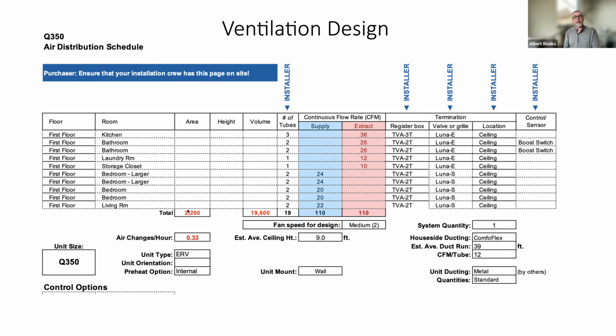It'll start getting dry, and it'll show up by cracked lips and skin and just general discomfort. So that happy medium we want to design for is we want to understand what the occupancy is and get plenty of fresh air for the occupants in a reasonable way in the right locations. And then we want to get the right amount of exhaust rate showing up. And we want to try to have those two numbers balance out with our relationship of airflow to physical volume of the building, which is that 0.2 to 0.25 all the way up to maybe 0.5 air exchange rates. And when we do that, then we create that really nice space.